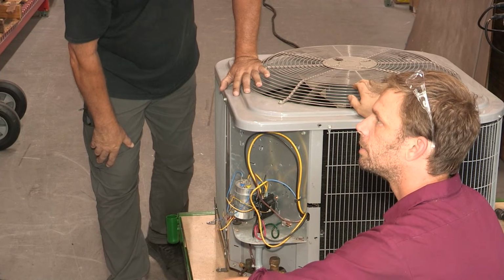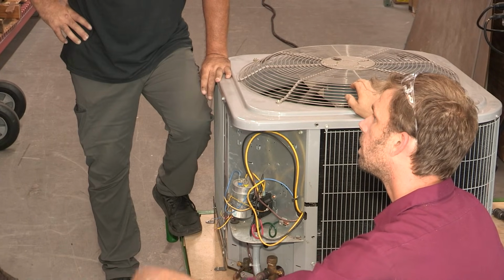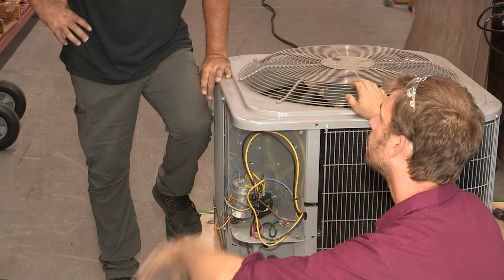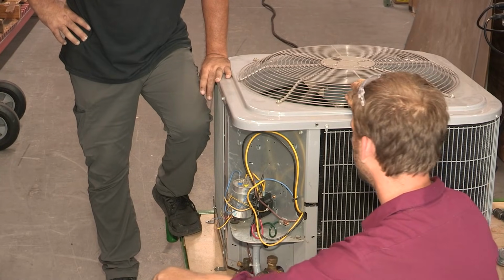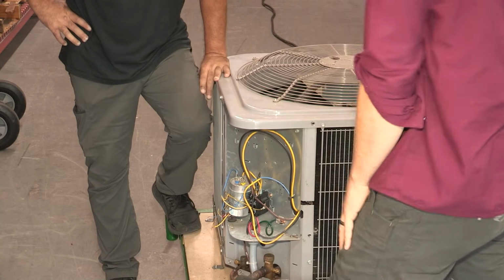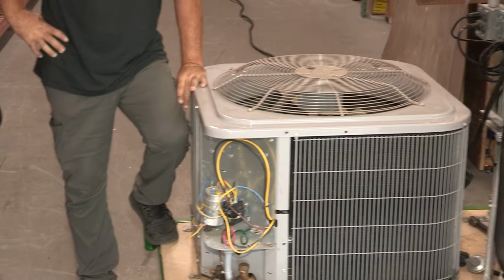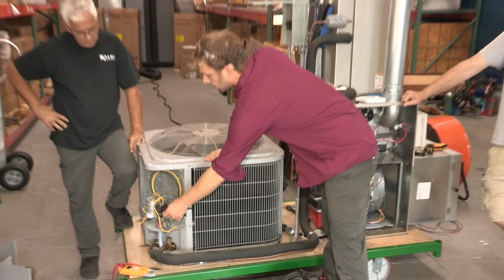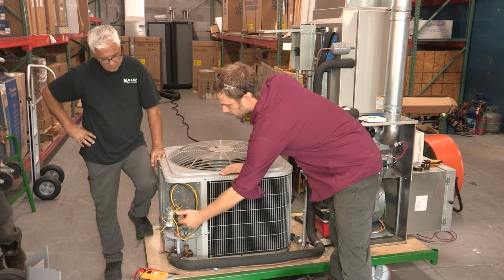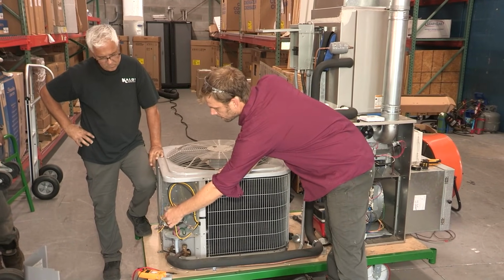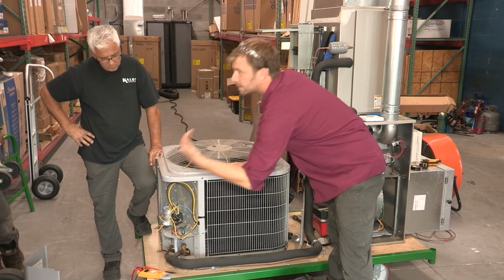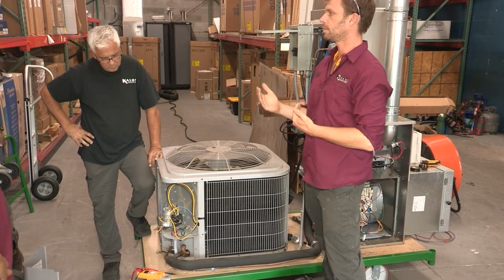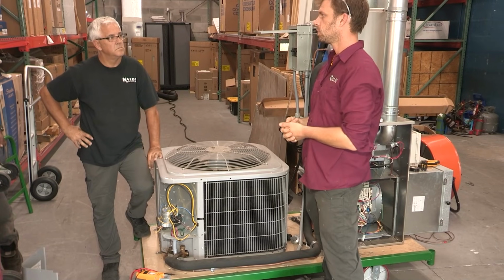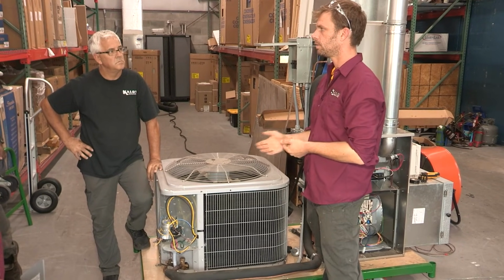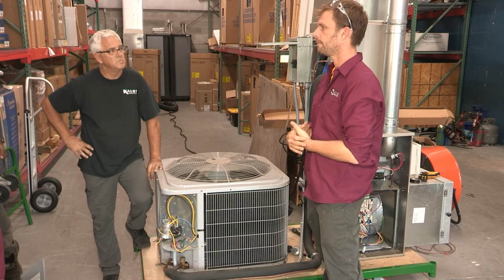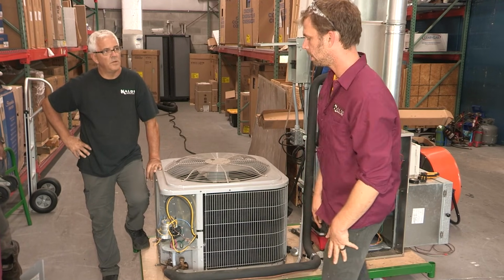Why doesn't it blow a fuse? What slows down the current? Resistance. The coil. Where's the coil? Within the contactor. Exactly. So that coil actually generates a load that creates resistance, and it slows down the current that's trying to get to ground, but it slows it down enough that we don't exceed 3 amps. We don't pop our fuse. So maybe we have an issue there. We've got to check the ohms on the... Yeah. So let's check the ohms on the contactor.